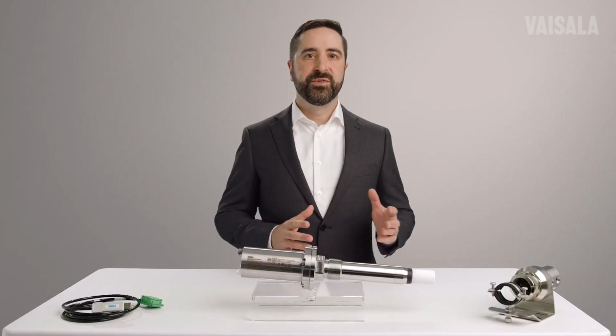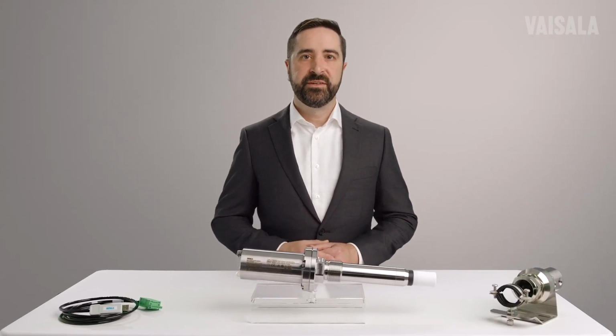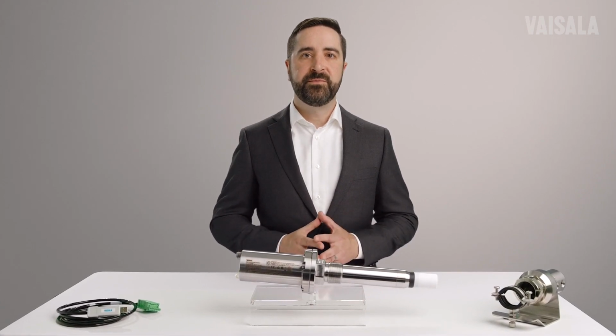These probes help monitor the methane slip from your upgrading system in real time with high accuracy, giving greater control over the process and quickly alerting operators to upstream issues. They can also be used for demand control switching of the separation media, maximizing the potential uptime for each membrane or column.